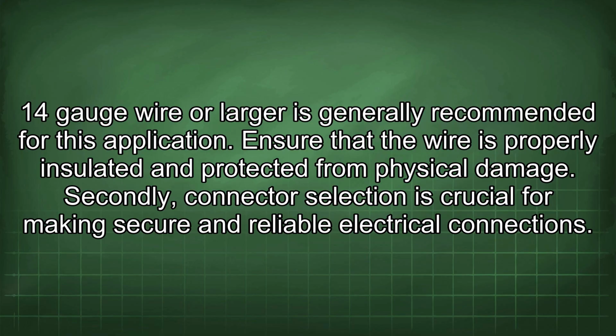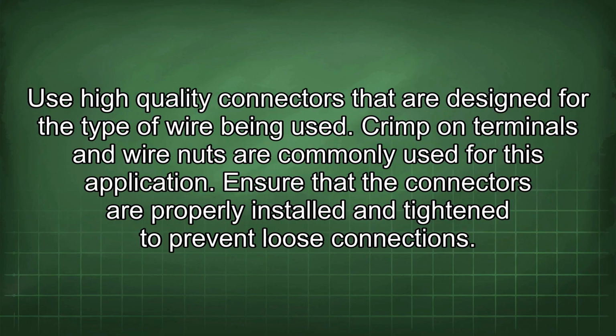Secondly, connector selection is crucial for making secure and reliable electrical connections. Use high-quality connectors that are designed for the type of wire being used. Crimp-on terminals and wire nuts are commonly used for this application. Ensure that the connectors are properly installed and tightened to prevent loose connections.